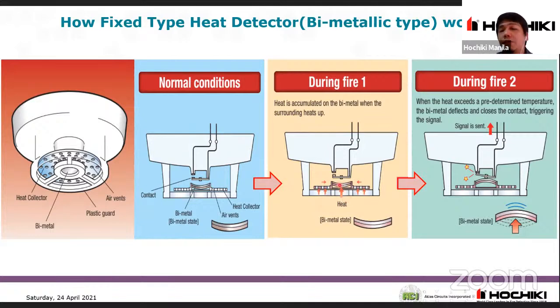When the heat is enough for this heat detector, for example, let's say we set the sensitivity at 135 degrees Fahrenheit. Once it reaches 135 degrees Fahrenheit, the bimetal plate will bend. When it bends, it makes contact at the top. Once that contact touches, that's when it gives a signal to our fire alarm control panel. That's how the fixed type heat detector, bimetallic type, works.